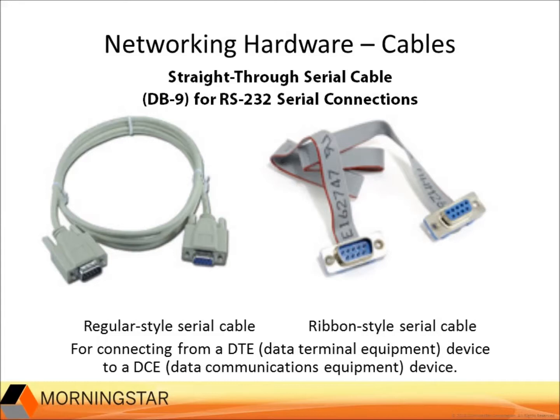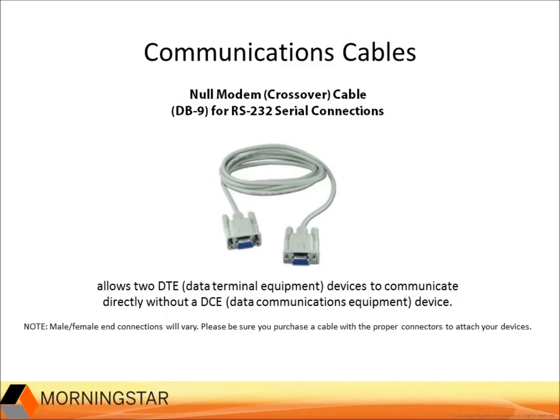The straight-through cable is used when connecting from data terminal equipment like a PC or Morningstar controller to data communications equipment like a modem. If you want to connect directly from a PC to a Morningstar controller or inverter without any data communications equipment, a null modem crossover DB9 RS-232 serial cable would be used instead of a straight-through cable.